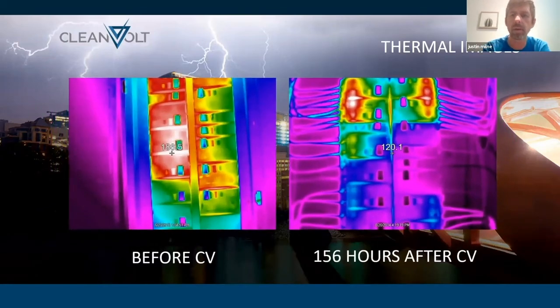156 hours later, after the unit was installed, you can see there is a significant difference in the heat dynamic on this panel. Of course, there are still some hot spots in the panel. It's important to keep in mind that whether it comes to heat damage or previous surge damage caused to components, CleanVolt nor any other device can reverse damage caused by that energy surging already. So this panel in particular, we confirmed with the customer that it had been in service for 10 years, 8 of which under extreme heating condition.